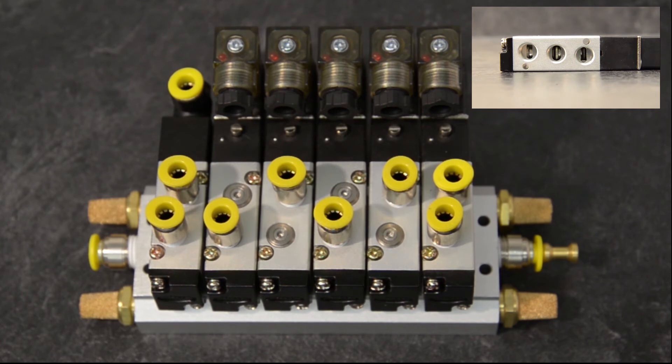In order to get a normally open three-way, we plug the B port and leave the exhaust ports open. In order to get a normally closed three-way, we plug the A port and leave both exhaust ports open.